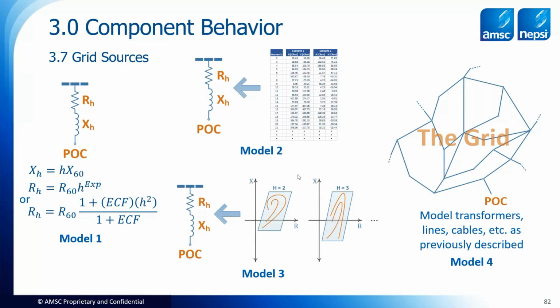Typically, these polygons are made by simulating thousands of cases in some automated script, okay? And they simulate all these, this line is literally hundreds, if not thousands of cases to build this characteristic. And then they say, well, we'll just put a box around it and say, you have to be within the box, okay? Again, pulling from these is very difficult.